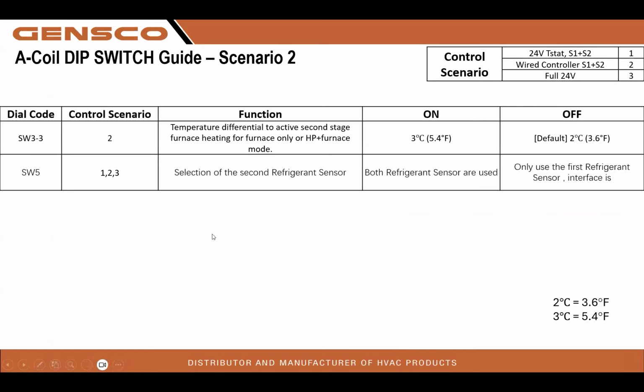SW5, remember, SW5 is for our refrigerant leak detectors. Remember, on this board, there are 2 spots, a black and a red. If SW5 is in the on position, you will get an error code. Make sure that your refrigerant leak detector is plugged into CN8, and it is the black plug on the board.